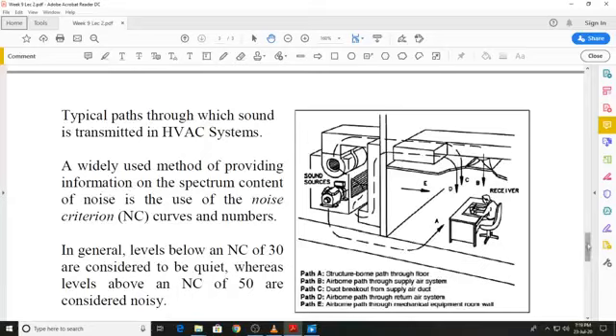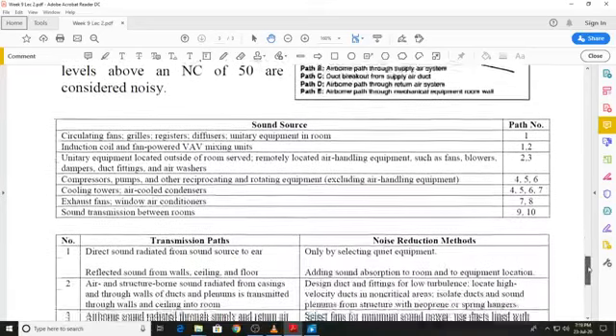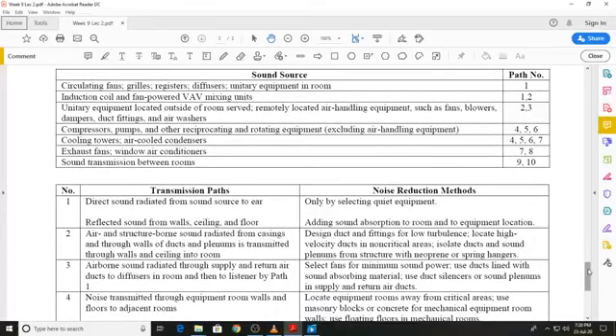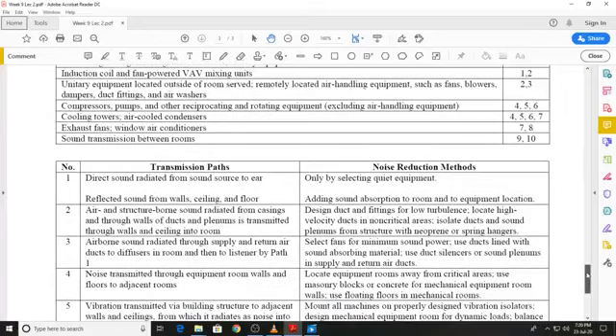And if you look at the ASHRAE handbook, they have given us a table of the sound sources, again typical of an air conditioning system, and the various paths through which those sounds are transmitted into the conditioned space. So the sound source is identified, and against that sound source you are given a number, which is its path number. In the next table you can see those path numbers given over here, and against those path numbers you are also given the recommended noise reduction methods.